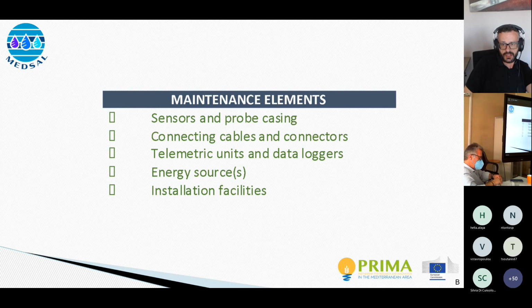Whether these sensors are installed underwater, at the wellhead, or in open air, extra care should be given to ensure the integrity of telemetric units and data loggers. Depending on where each unit is installed, things to inspect include protection against humidity, which can significantly harm your equipment, and the integrity of casing. If housing is soiled or filled with insects, it is a very common problem. Housing can also be damaged by animals or vandalized by people — we have seen birds, foxes, or cows damaging the cables and instruments.